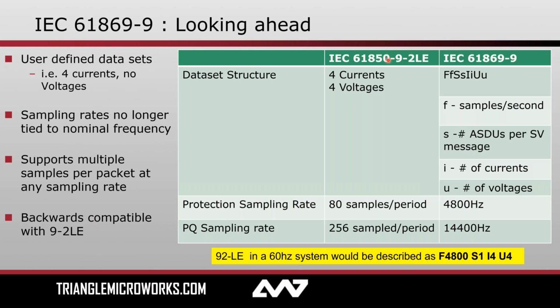This chart just compares and contrasts. This column right here is how we come up with a string that defines a specific 61869-9 implementation. F refers to the samples per second. S is the number of ASDUs per sample value message, the number of samples that I want to include. So instead of sending out a new packet every time I take a sample, I could wait for 2, stuff them together, and then send it out. I and U are the number of currents and voltages. So what you end up with is a string that looks like this down here at the bottom. And this would define a 9.2 LE system that is 60 hertz: F4800, S1, I4, U4.